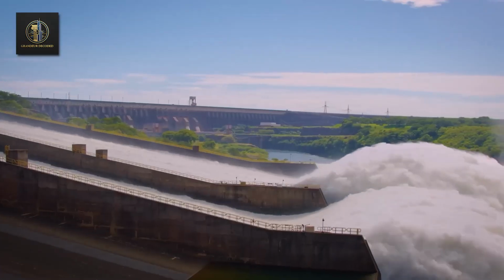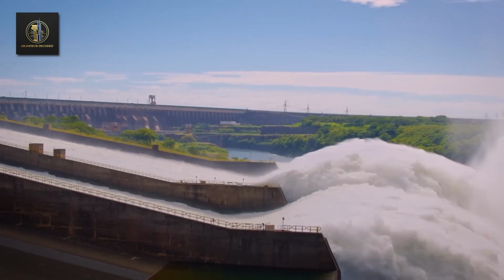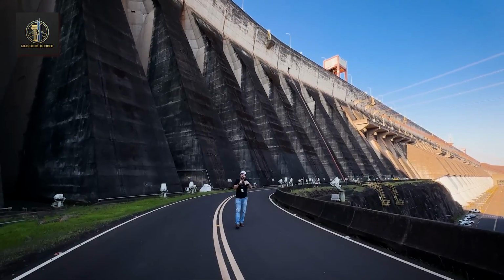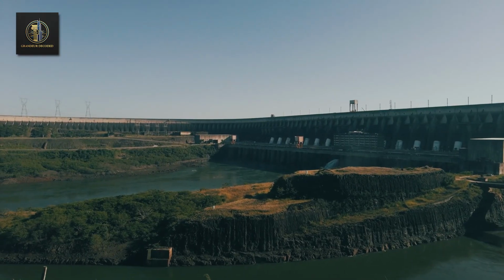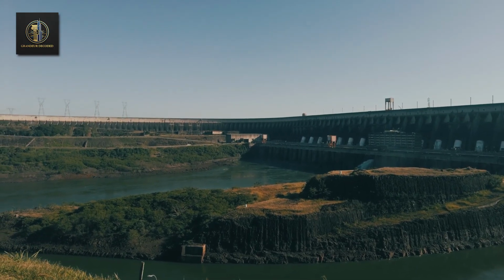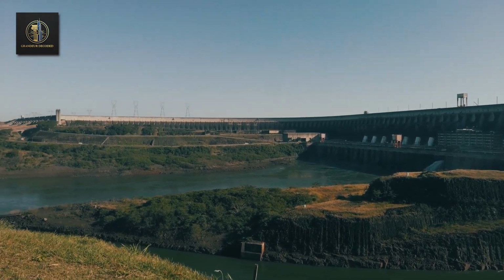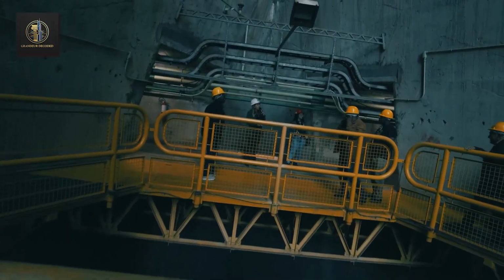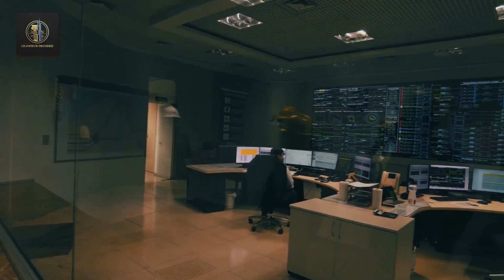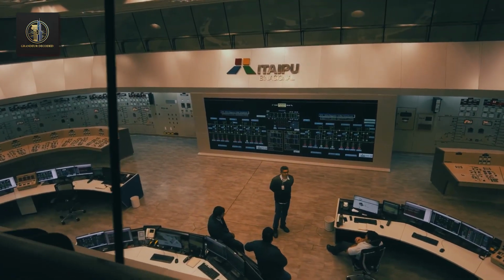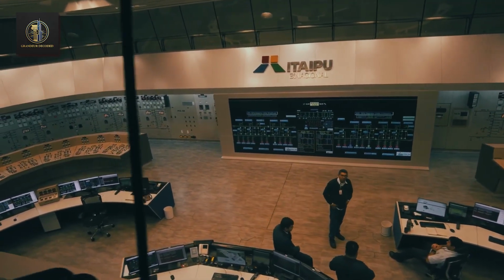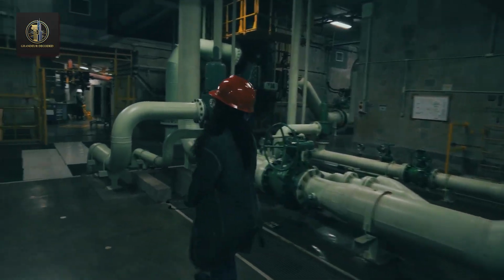Fact 7. The powerhouse contains 20 generating units, each rated at approximately 700 megawatts. Water enters through massive penstocks and drives Francis turbines engineered for high efficiency under variable head conditions. Blade geometry, rotational speed limits, and pressure tolerances were optimized to prevent cavitation and vibration across a wide operating range.